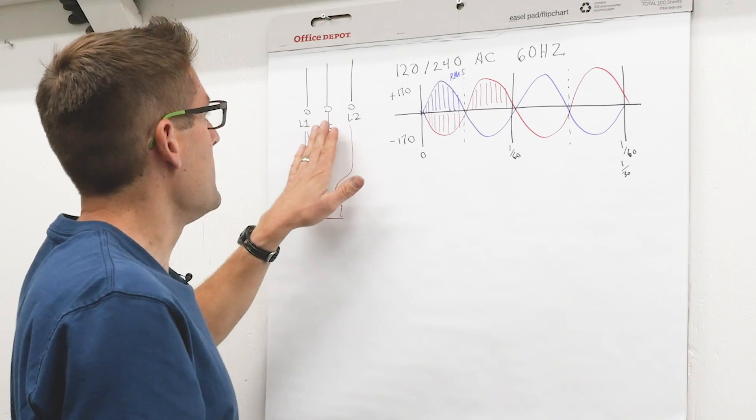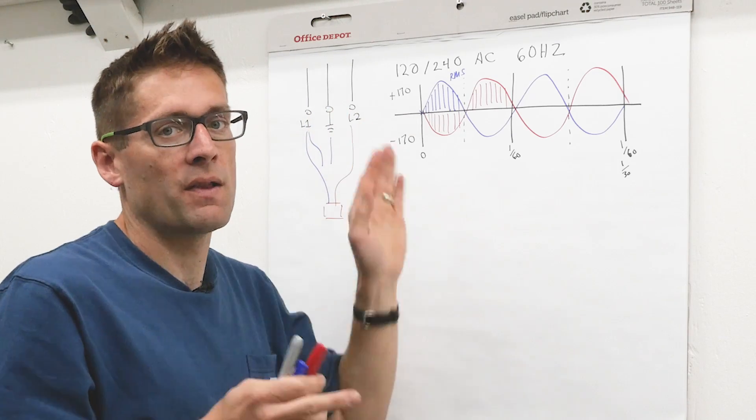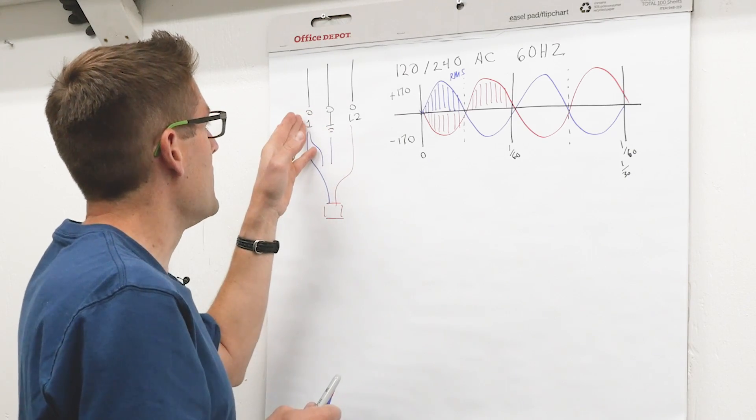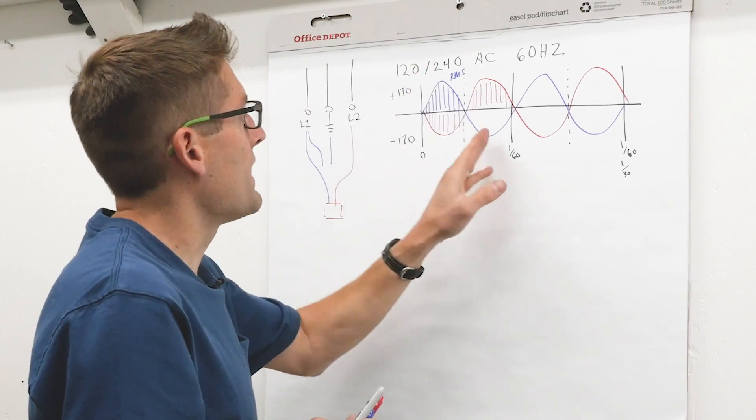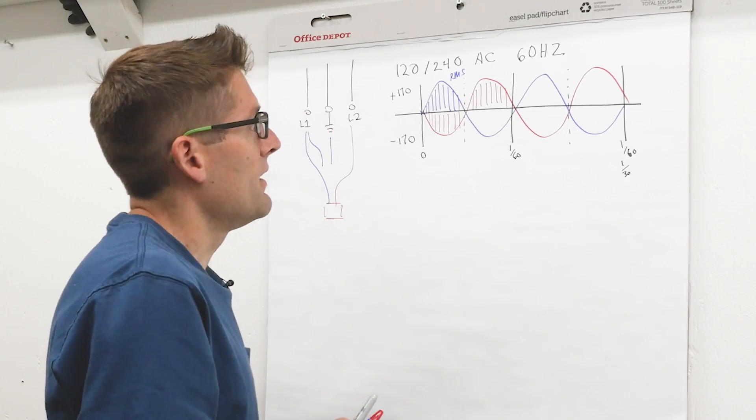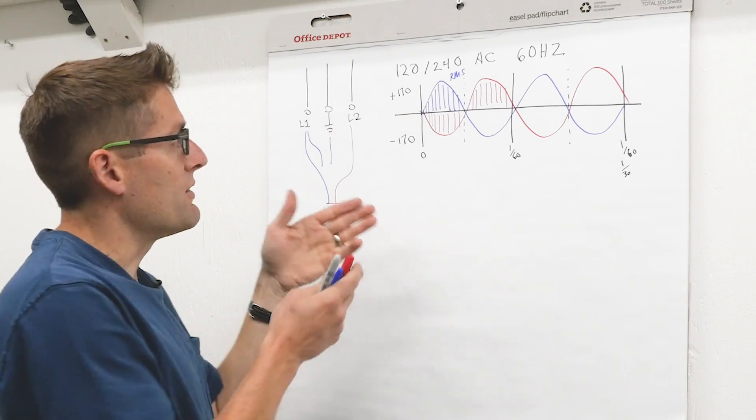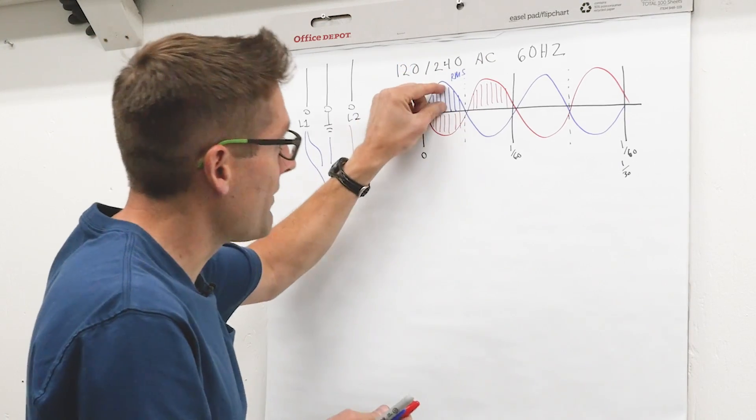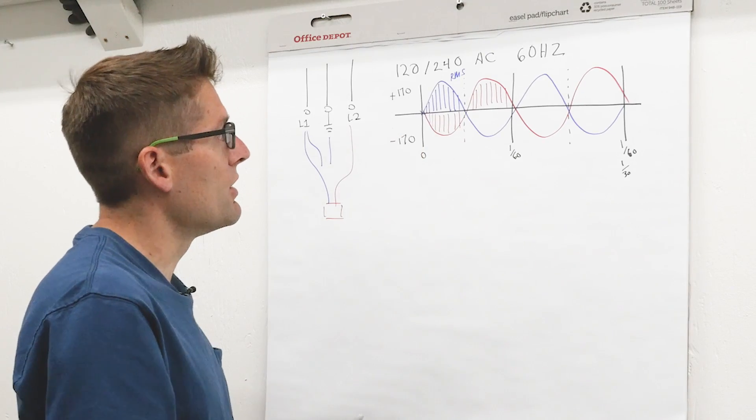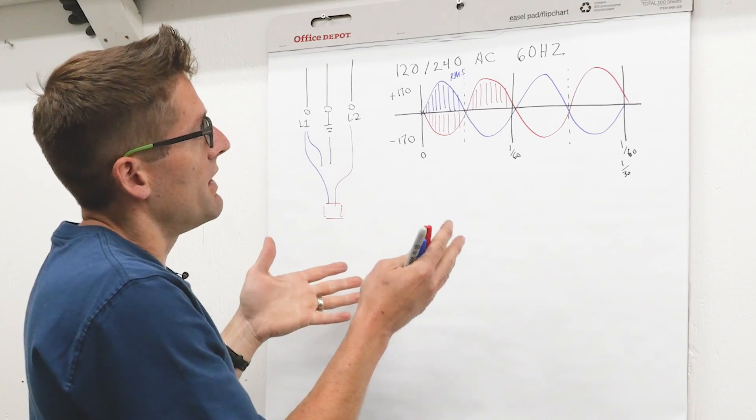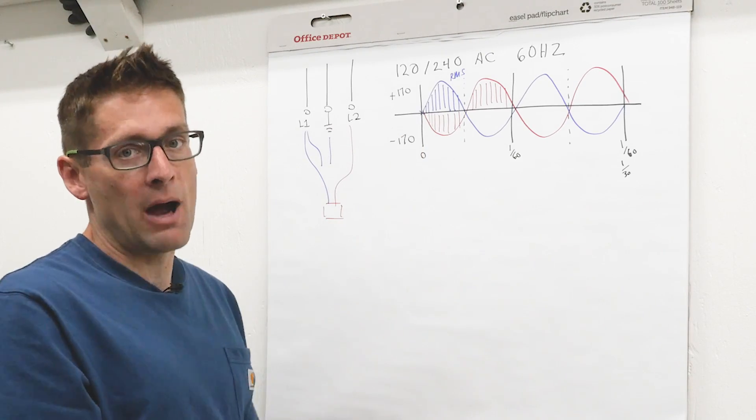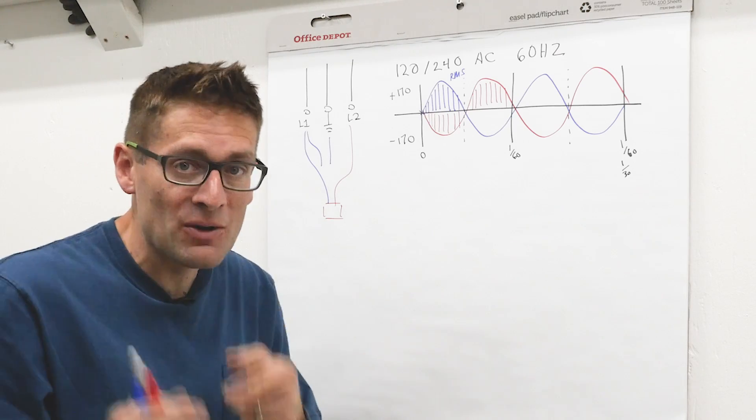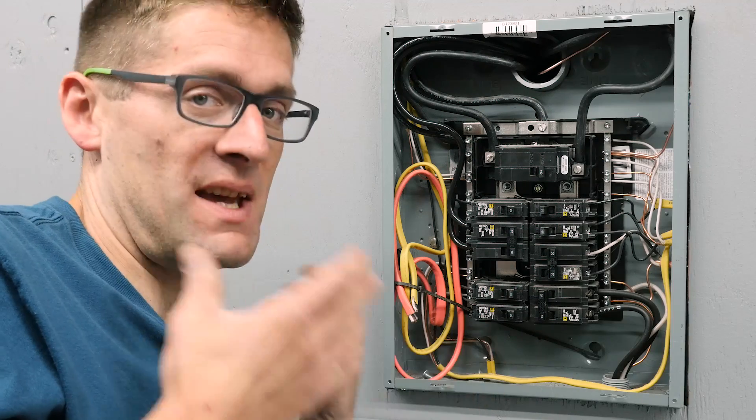So if you understand that the neutral is like ground but is slightly different and does not have potential, L1 alternates plus 170 negative 170, L2 is the opposite, the RMS power averages out to 240 volts for 240 single phase or half of that 120 if we're just going to the neutral. This will kind of let you understand what you need to know about power for single phase in a shop. Let's go over the electrical panel and I'll show you what that actually looks like and this is where things get practical.